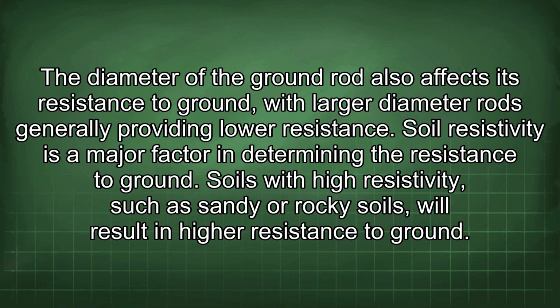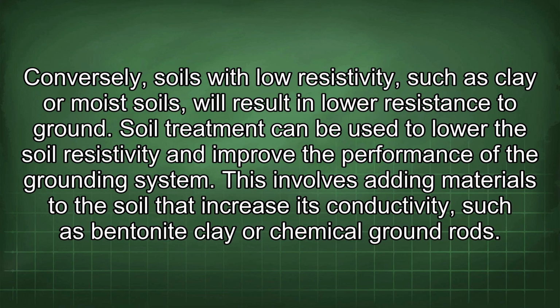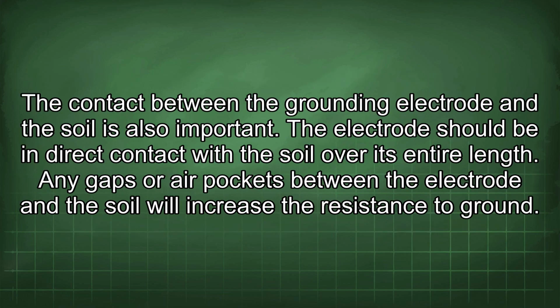Soil resistivity is a major factor in determining the resistance to ground. Soils with high resistivity, such as sandy or rocky soils, will result in higher resistance to ground. Conversely, soils with low resistivity, such as clay or moist soils, will result in lower resistance to ground. Soil treatment can be used to lower the soil resistivity and improve the performance of the grounding system. This involves adding materials to the soil that increase its conductivity, such as bentonite clay or chemical ground rods. The contact between the grounding electrode and the soil is also important. The electrode should be in direct contact with the soil over its entire length.